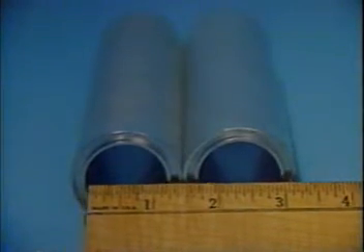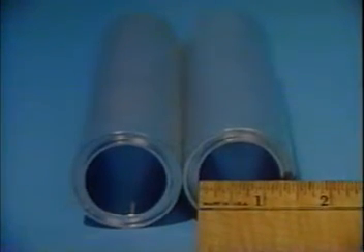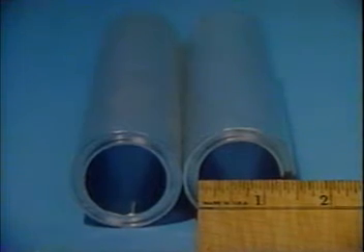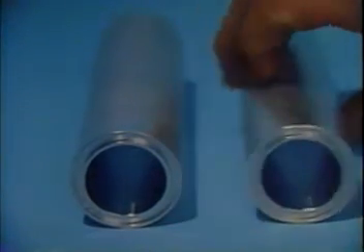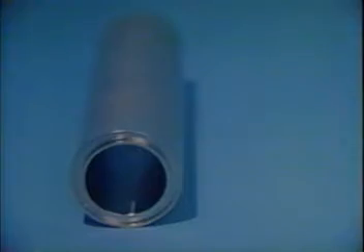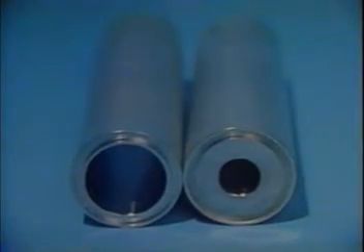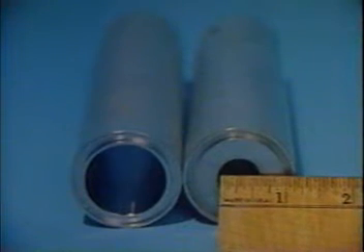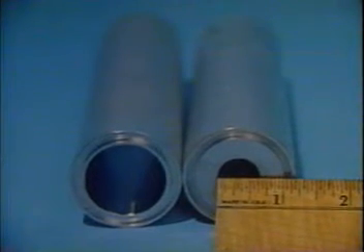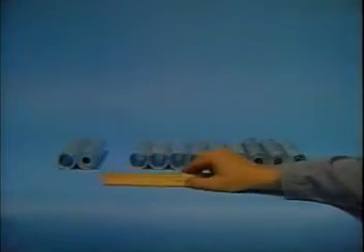Identical pump dimensions give a 1-to-1 volume ratio. Replacing one pump with a pump of different dimensions as required to obtain a particular ratio for a different chemical formulation makes many volume ratios possible.